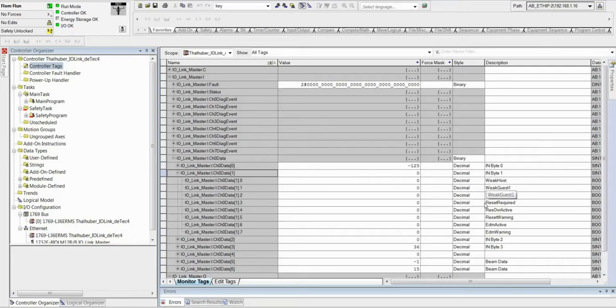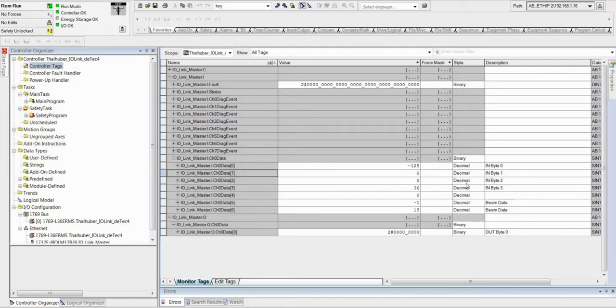Here's where we get weak signal strength signals. So the importance there is we can predict maintenance when the curtain needs to be realigned. Some other things we can do with this signal is tell when the lens needs to be cleaned. Moving on to in byte 2.